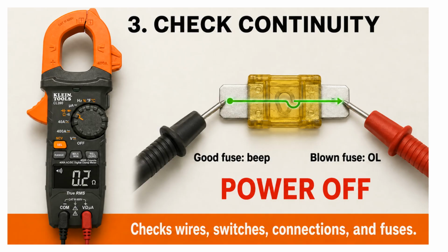Turn the selector dial to the orange ohms and continuity position. Use the SEL button to choose continuity mode. Touch the 2 probe tips together. The meter should beep. This quick check tells us the meter and leads can see a complete path.